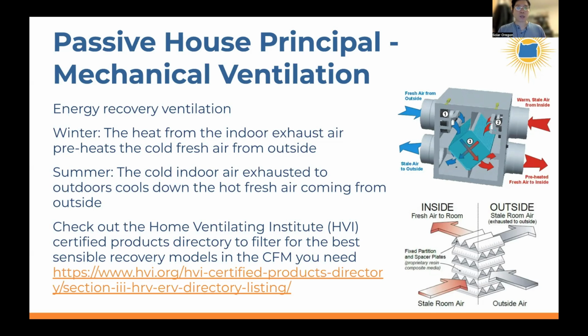Passive house mechanical ventilation involving energy recovery is another principle. These units typically come with a MERV 4 or MERV 8 filter, but you can buy upgrade filters that go up to MERV 13 or higher, which is great for filtering out wildfire smoke and vehicle pollution, giving you really high quality filtered air through your mechanical ventilation system.